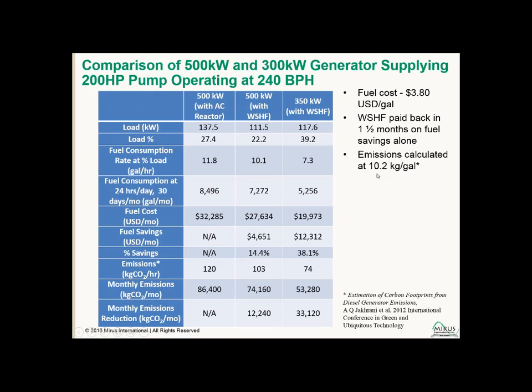So we used a calculation of 10.2 kilograms per gallon, which came out of an IEEE paper. And at that level of emissions, we were running before at 120 kilograms of CO2 per hour, and that dropped to 103. On a monthly level, it dropped from 86,400 to 74,000, a reduction of 12,240. So a substantial reduction in the emissions sent into the environment.